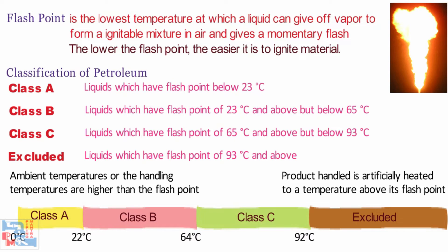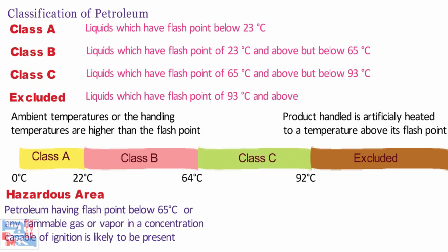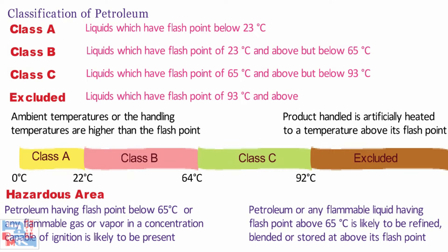An area will be deemed hazardous where petroleum having a flashpoint below 65 degrees Celsius, or any flammable gas or vapor in a concentration capable of ignition, is likely to be present. Petroleum or any flammable liquid having a flashpoint above 65 degrees Celsius is likely to be refined, blended, or stored at above its flashpoint. Liquefied gases like LPG and LNG do not fall under this classification but form a separate category.